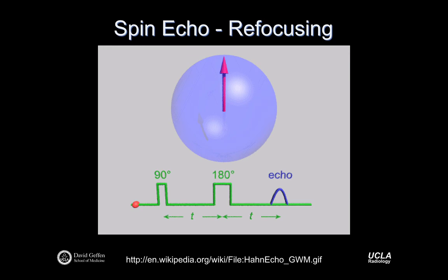Those spins at different positions actually see slightly different fields. The B0 is not perfect, there's a chemical shift effect, susceptibility, something. As a consequence of not seeing the same field, they're going to fan out. In the rotating frame, they would otherwise all point in the same direction, but if you have a slightly different B0, you're going to drift to the left or drift to the right, depending on the specific field you're exposed to. Then in the middle is this refocusing pulse, which flips everything over like a pancake. Then those same sources of off-resonance will actually push the spin system together.